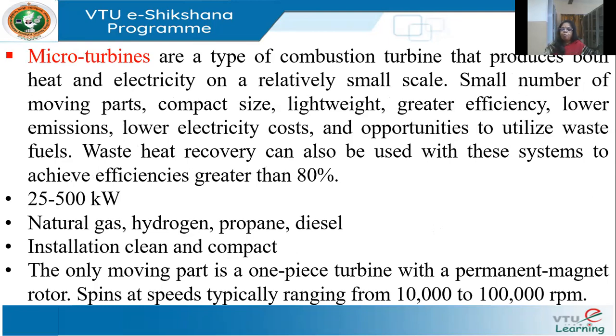In this category we also have micro turbines — a type of combustion turbine that produces both heat and electricity on a small scale. They have fewer moving parts, are compact and lightweight, with good efficiency, lower emissions, and lower energy cost. You also have an opportunity to utilize waste fuels. Because the heat is recovered, the entire cycle efficiency is around 80%, which is pretty high. They are normally used in the range of 25 to 500 kilowatts.